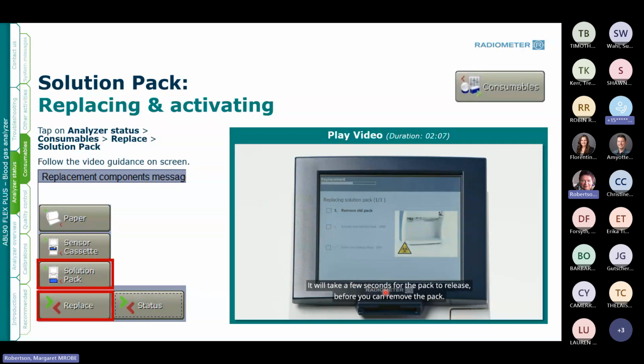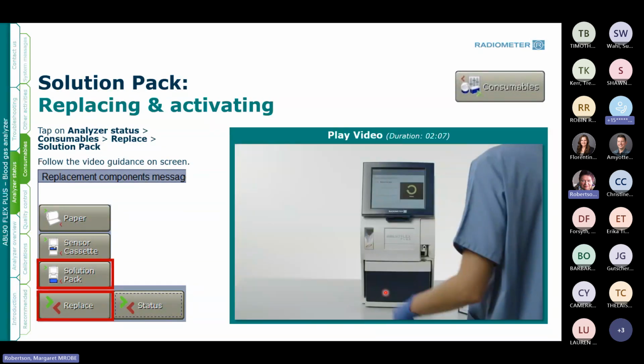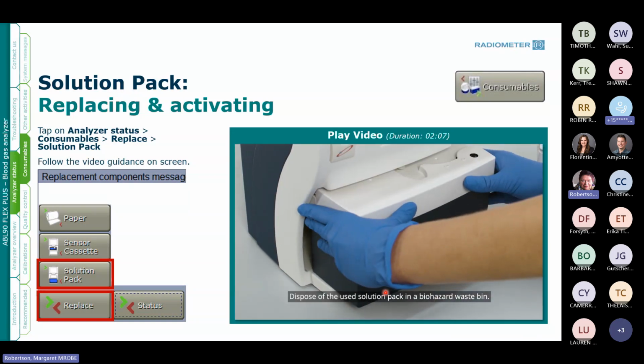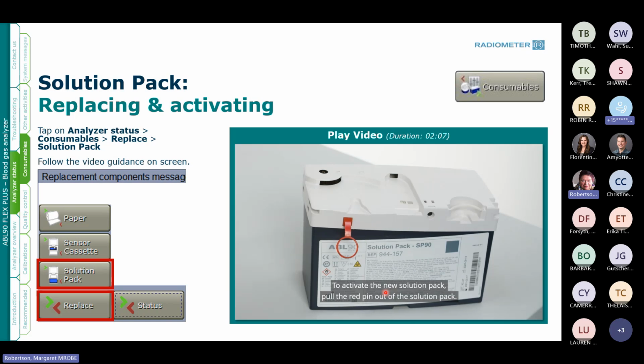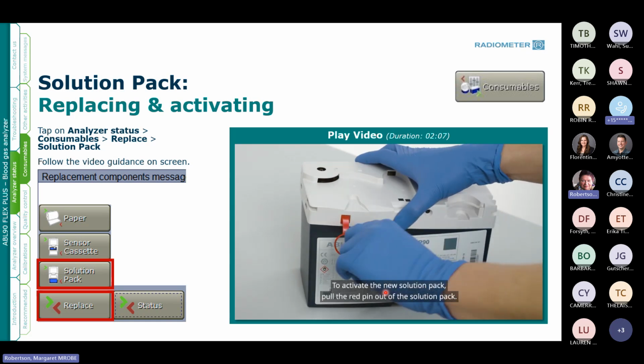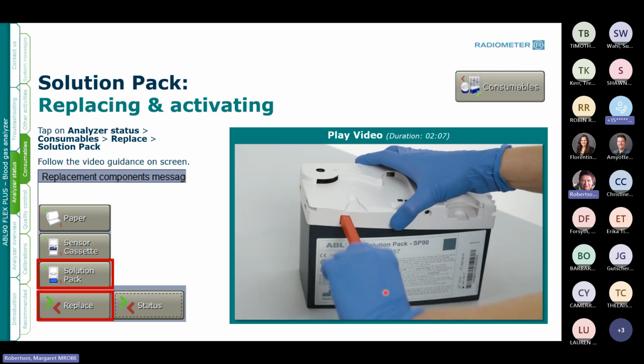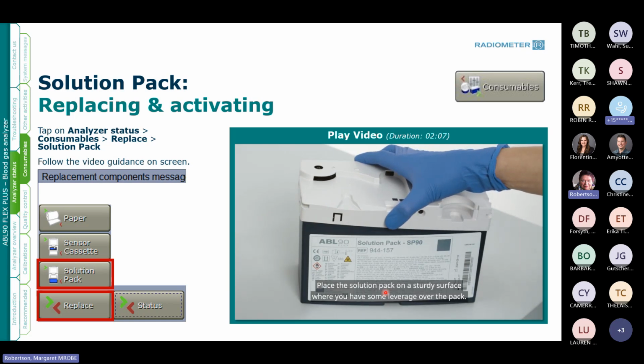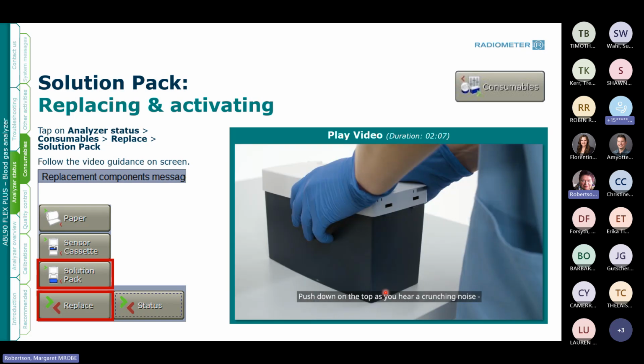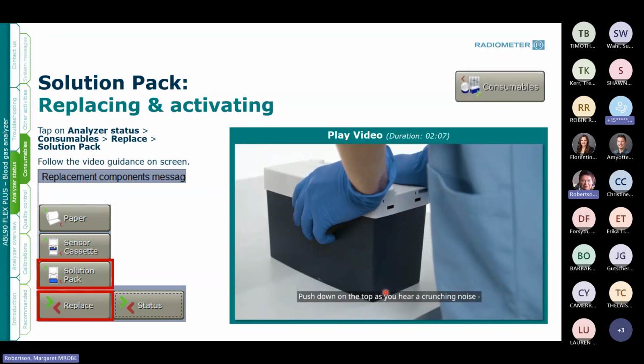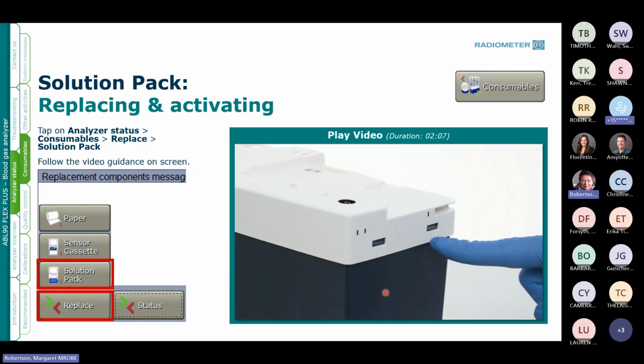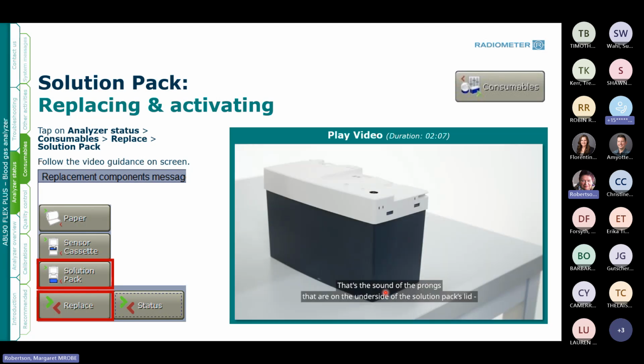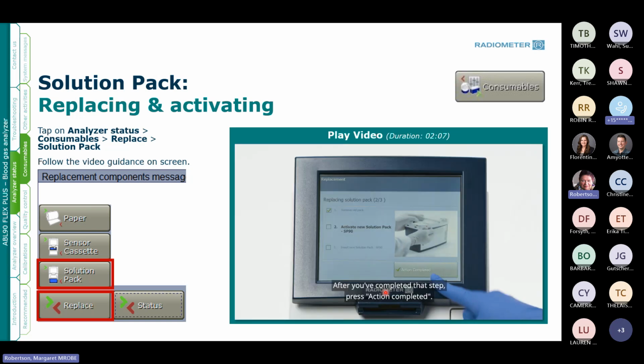The inlet will open automatically, and the video will show you how to remove the solution pack. It will take a few seconds for the pack to release before you can remove it. Dispose of the used solution pack in a biohazard waste bin. To activate the new solution pack, pull the red pin out of the solution pack. Place the solution pack on a sturdy surface where you have some leverage over the pack. Push down on the top until you hear a crunching noise and both tabs click into place. That's the sound of the prongs on the underside of the solution pack's lid puncturing the pouches inside of the solution pack. Make sure you have activated the pack completely. After you've completed that step, press Action Completed.